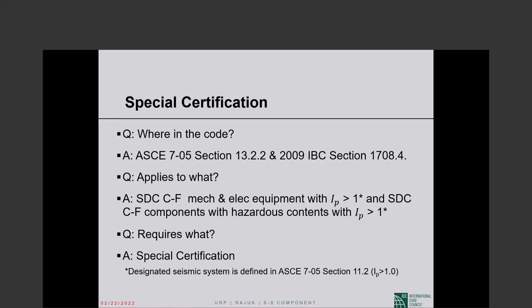Now, if you read ASCE 7, instead of straight out saying equipment with I sub P larger than 1, it talks about the designated seismic system, which consists of electrical and mechanical equipment with I sub P larger than 1. The definition is in section 11.2. Anyway, it boils down to what we said: you need special certification for design categories C through F mechanical and electrical equipment with I sub P larger than 1, and design categories C through F components with hazardous contents with I sub P larger than 1.